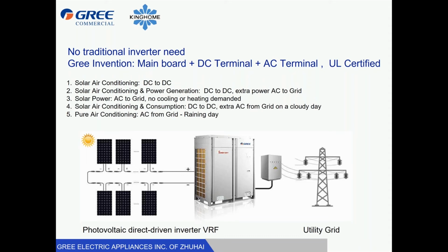So for example, we have a day that is cloudy. We don't have enough panels to generate enough power to run the unit. The inverter inside the unit will automatically draw enough power from the grid connection to power the unit. On the other side of things, if we have a sunny day and we have enough solar panels that will power more than just the unit, it can feed the power back into the building, and it can also sell power back to the utility grid if you set it up appropriately. So the inverter built into the unit eliminates the power inverter that you would usually buy separately.